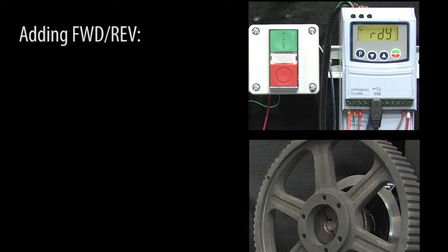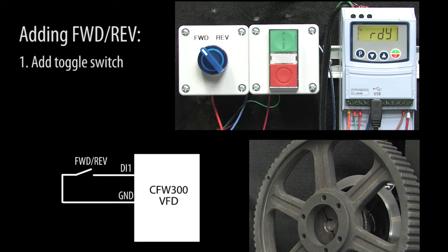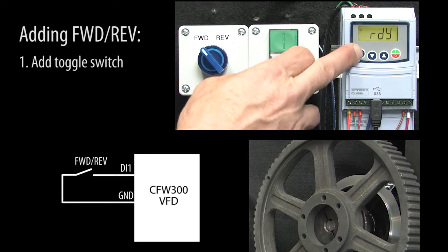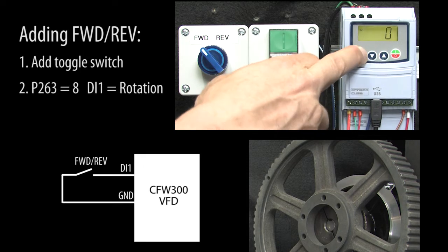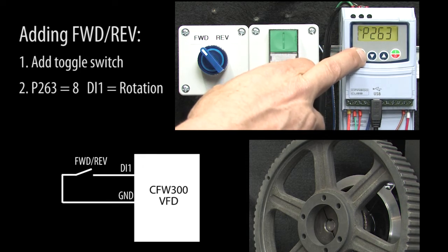Well, to add forward reverse control, we only need to do three things. First, add a toggle switch to digital input 1. Second, go to parameter 263 and enter an 8. That tells digital input 1 that it will be controlling the direction of rotation.